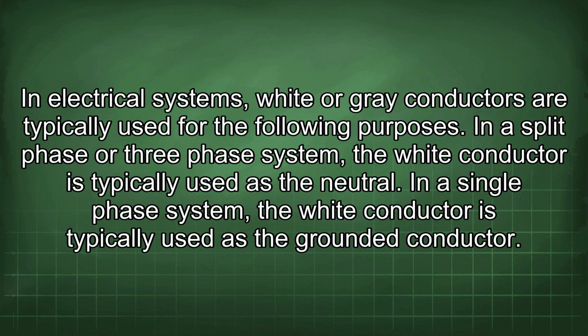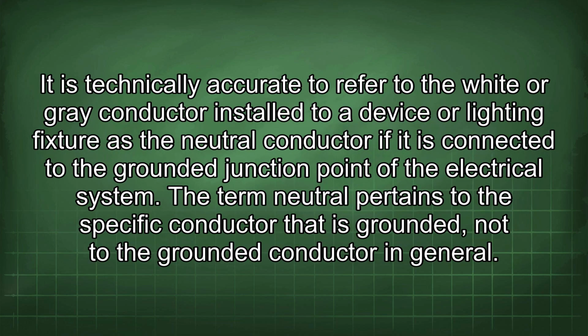In electrical systems, white or gray conductors are typically used for the following purposes. In a split-phase or three-phase system, the white conductor is typically used as the neutral. In a single-phase system, the white conductor is typically used as the grounded conductor. It is technically accurate to refer to the white or gray conductor installed to a device or lighting fixture as the neutral conductor if it is connected to the grounded junction point of the electrical system.